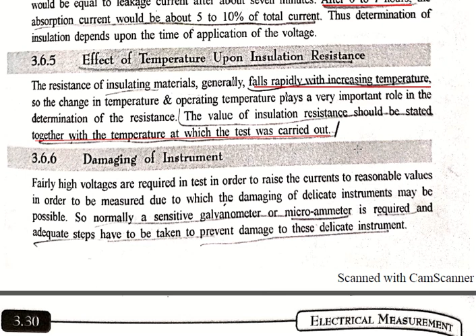Damaging of instrument is also a difficulty in measuring high resistance, because fairly high voltages are required in the test in order to raise the currents to reasonable values to measure the resistance. Due to this, damaging of delicate instruments may be possible. Normally a sensitive galvanometer or microammeter is required, and adequate steps have to be taken to prevent damage to these delicate instruments.